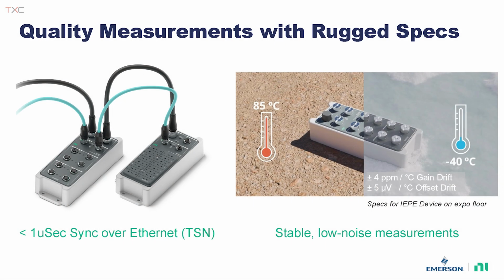There's 4 parts per million per degree C gain drift on the IEPE device, and then 5 microvolts per degree C of offset drift. So just really, really stable quality measurements that you're not going to get from like other vendors. There's other boxes out there that are IP67 DAQ devices, but we take the lab measurement quality outside.